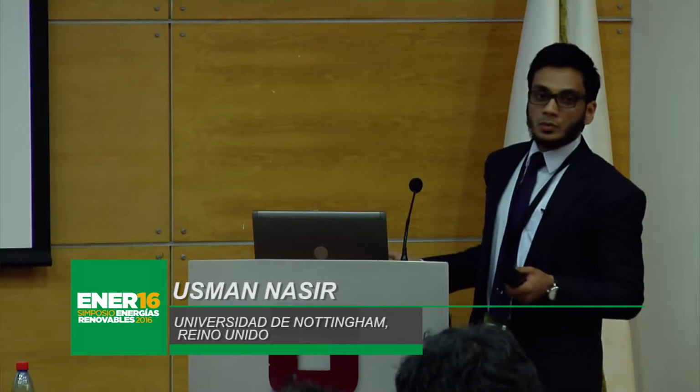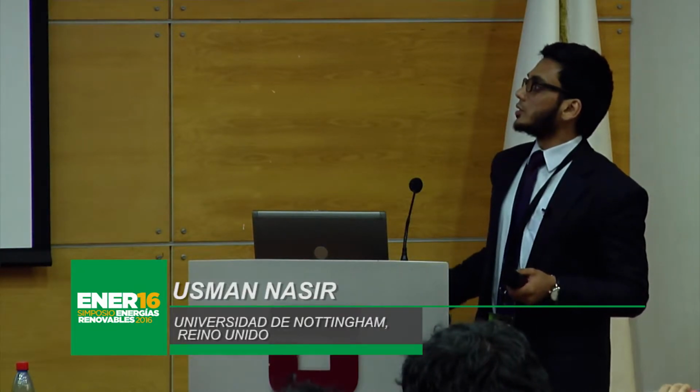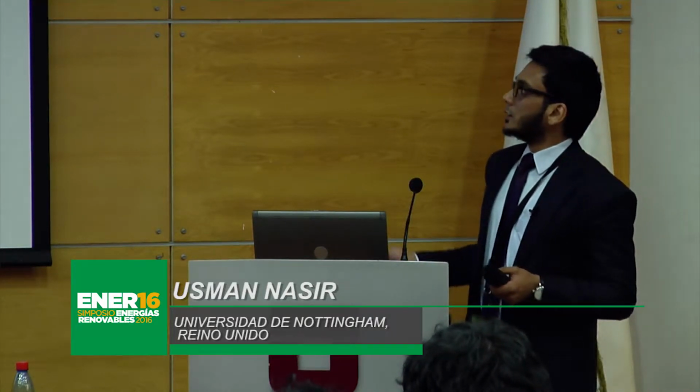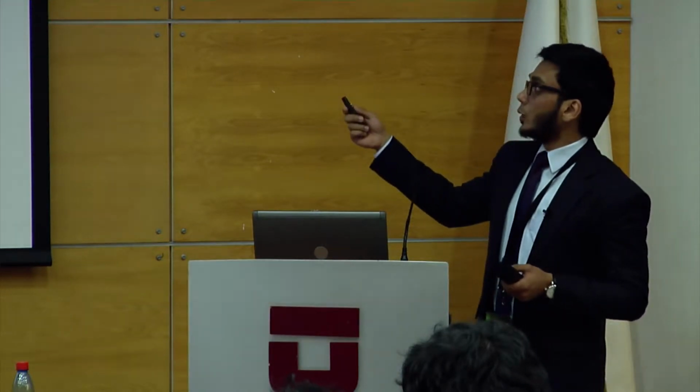What we can do is increase the operating frequency of the transformer, and the size will decrease. So we place the transformer between two power converters, and the transformer now works at a medium or high frequency range. We will only discuss this kind of topology because it is a cheaper solution, and it is not bulky or heavy.